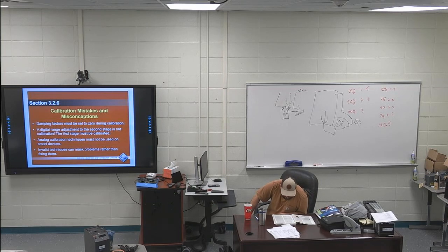Skip a sentence, and I've got the next two sentences highlighted. Settling time is the time the test or calibration process waits between sending the input to the device and reading the resulting output. For this reason, the device dampening value should always be set to 0 before performing any test or adjustment.